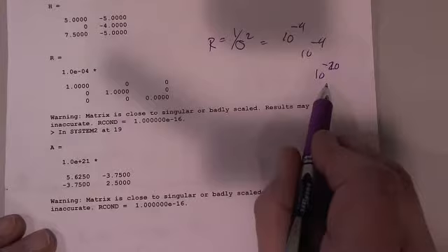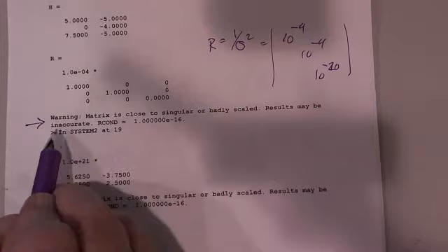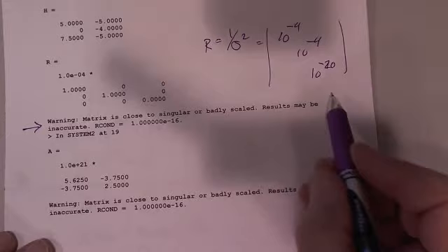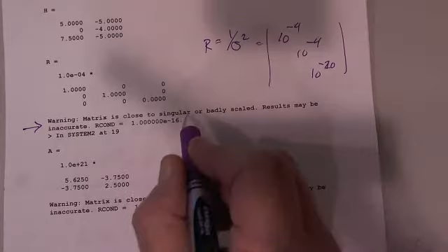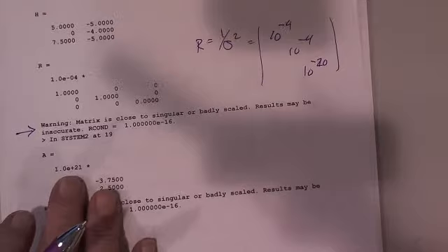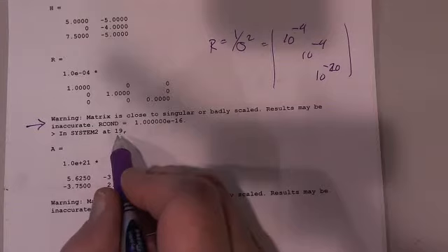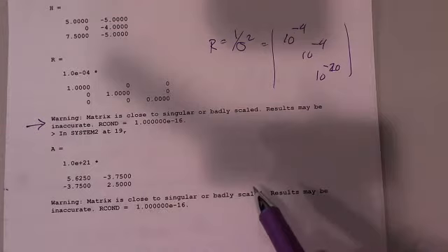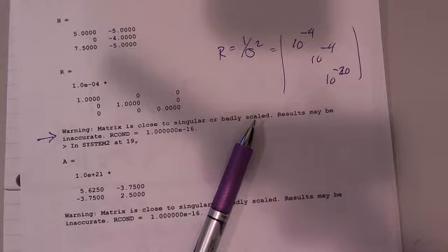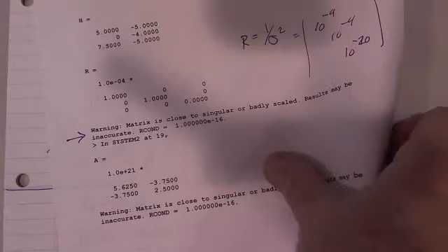When you go to solve it, there's MATLAB saying warning: matrix is close to singular and badly scaled. Results may be inaccurate. There's a thing called the condition number that you can calculate, and this condition number is e to the minus 16. This is the line in the MATLAB code, and when you go to do something with it, you can't go forward. You can't solve anything. This was this little 3-bus system with a zero injection.